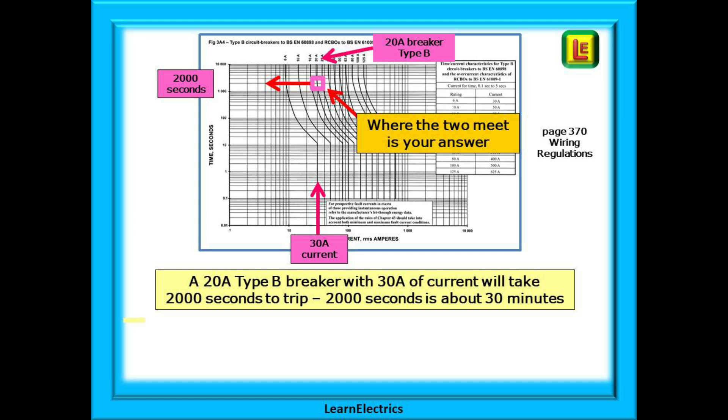Trace this crossing point to the left and read off the number of seconds it takes to trip. In this case it is 2,000 seconds, just over 30 minutes.